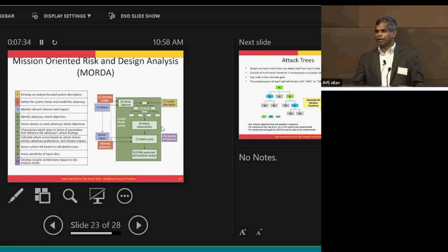If those maintenance and upgrades are not done well, that will lead to blackout. That's what happened in India, the largest blackout in history. During maintenance of one of those ultra high voltage lines, there was some miscommunication that led to overload in other lines, the cascading. There were other phenomena too, but it was related to maintenance as well. Yeah.